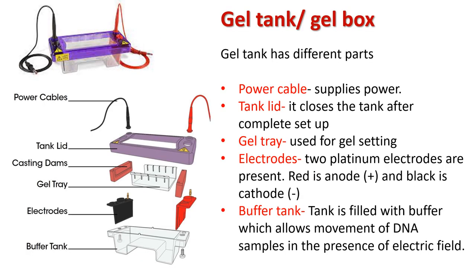The gel tank or gel box has several parts. The power cable supplies power. The tank lid is made of plastic and closes the tank after complete setup. The gel tray is used for gel setting. Two platinum electrodes are present — red is the anode and black is the cathode. The buffer tank is a plastic container with a raised center where the gel is placed. The tank is filled with buffer, which allows movement of DNA samples in the presence of an electric field.